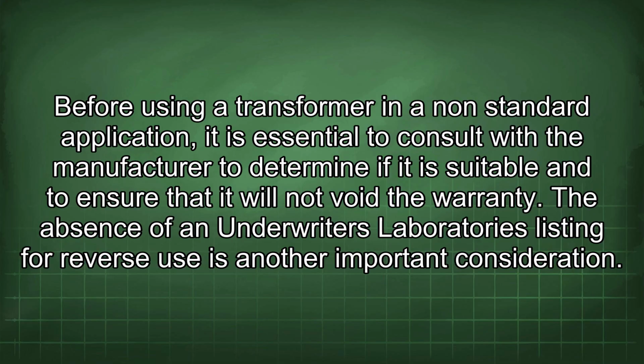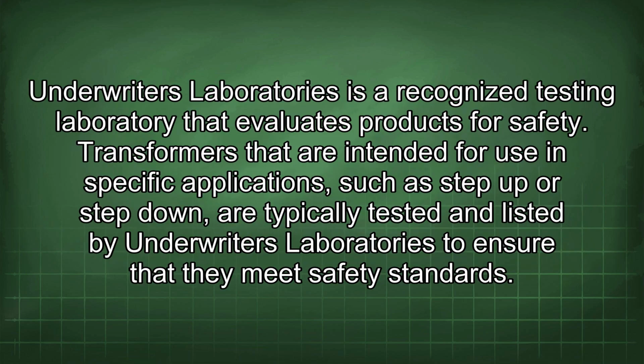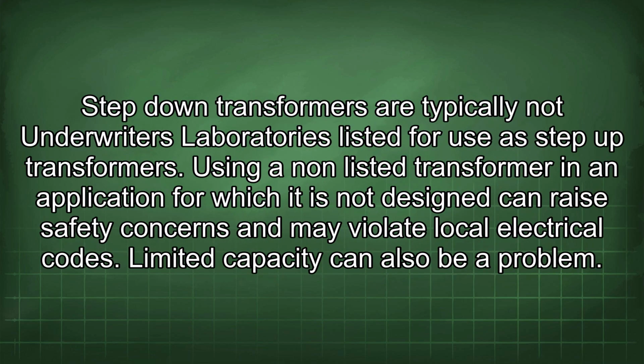The absence of an Underwriters Laboratories listing for reverse use is another important consideration. Underwriters Laboratories is a recognized testing laboratory that evaluates products for safety. Transformers that are intended for use in specific applications, such as step-up or step-down, are typically tested and listed by Underwriters Laboratories to ensure that they meet safety standards. Step-down transformers are typically not Underwriters Laboratories listed for use as step-up transformers. Using an unlisted transformer in an application for which it is not designed can raise safety concerns and may violate local electrical codes.